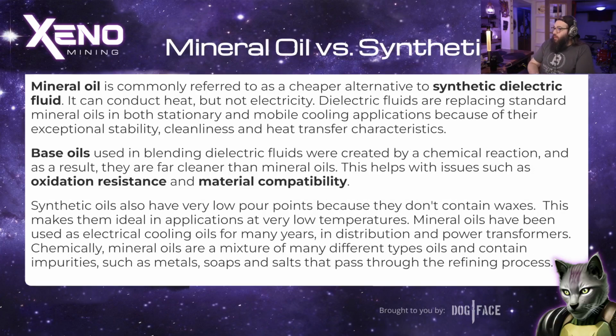All right, let's talk about the difference between mineral oil versus synthetic oil. Mineral oil is cheaper and more accessible. If you're going to begin immersion mining, you might think getting the engineered fluid will be much more expensive right now, but with mineral oil you can get started right away. Mineral oil can absolutely be used, but if longevity is what you're after, we might think a little differently about that.